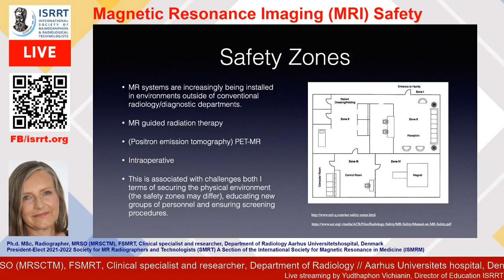When we move on to labeling, we sort of have two types. We have the labeling for equipment that may be brought into zone 4, and then we have the labeling of implants. But as you can see here, the symbols are what we're going to use in the future. Those are MR safe, MR conditional, and MR unsafe. And MR safe is easy because MR safe is non-metallic, non-conducting objects that can be brought into the scanner room, whereas MR unsafe should never go near the magnetic field.